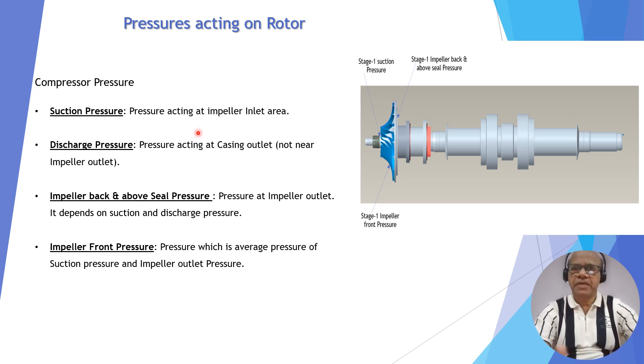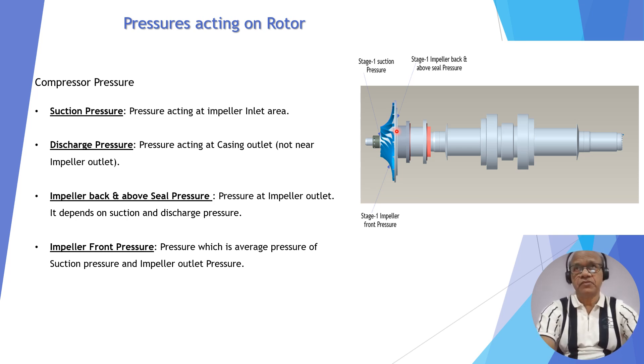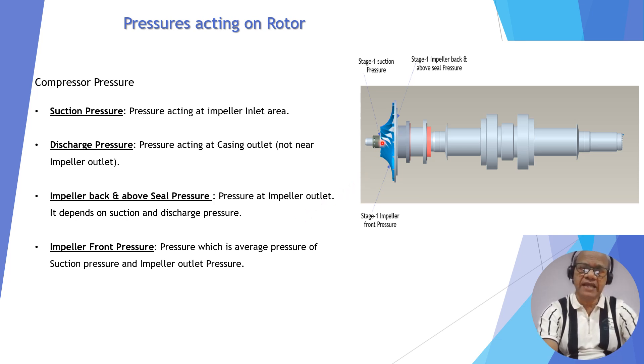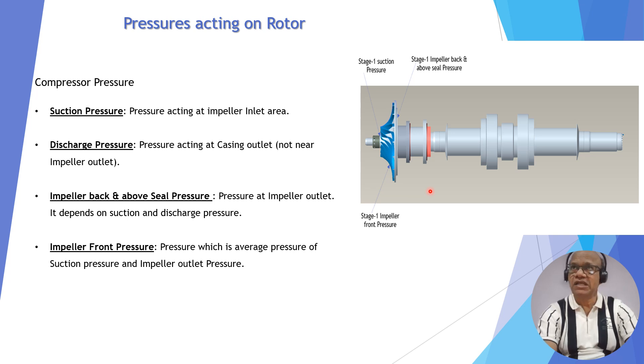Once the impeller geometry is fixed, its dimensions are also fixed — there is no change in geometry, no change in dimension. So there will only be a change in pressure. Force is the product of area multiplied by pressure. Since area is not going to change, the only variable is pressure. The pressures acting on the rotor are: suction pressure acting on the impeller inlet portion, compressor discharge pressure at the casing outlet — not the impeller outlet — and the impeller back pressure above the wheel seal.